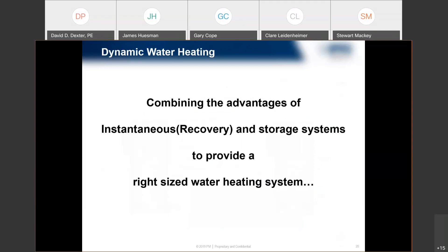What we're going to talk about now is what we call dynamic water heating — taking the concept of designing around instantaneous but coupling it with storage. By instantaneous, that's basically recovery. If you design a building targeting 100 GPM and you're designing for instantaneous, you have to design for 100 GPM regardless of whether you couple any storage. You're also designing that system for 100% of combustion air requirements, 100% of venting, and 100% of fuel — it's all the ancillary factors supporting those pieces of equipment.